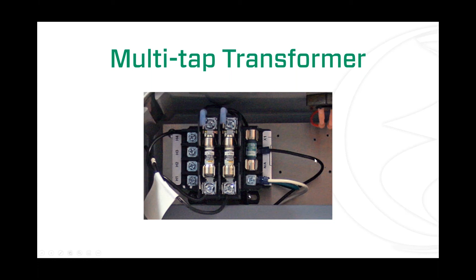The next thing that I want to mention here is these intrinsically safe modules. These are going to be used in what we call a hazardous environment location. Sometimes people refer to that as explosion proof. These will officially be called out as Class 1, Division 1, Group C and D locations, or another rating is Class 1, Zone 1, Groups 2A and 2B. So an intrinsically safe module may look different. There's different types out there, and even in our control panels, you might get one that looks a little different than this. This is probably the most common one we use at the moment.